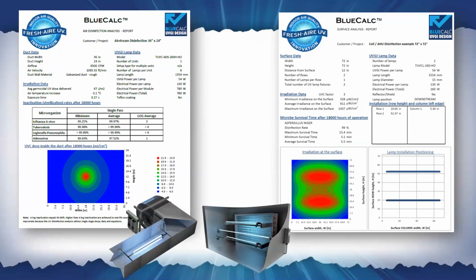This is how well understood the technology is, that we could have these simulations in hand before a decision's even made. We take those parameters, the CFM, the duct dimensions, the coil dimensions, and put that into our calculation software. We choose the length of lamp and the number of lamps, and it gives us the dosage, the intensity, the real-time neutralization rate on a single pass or multiple passes. It shows us where the UV is being irradiated.